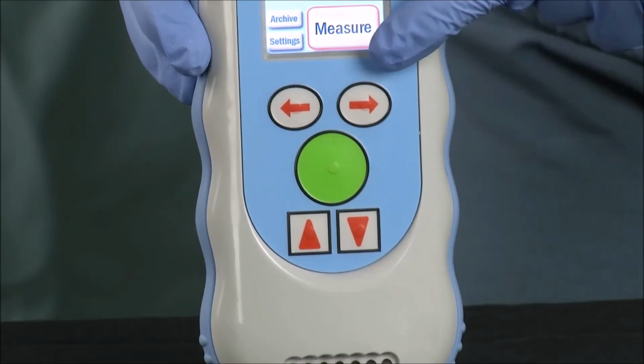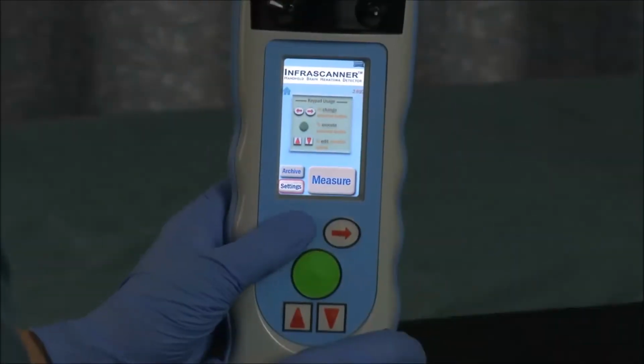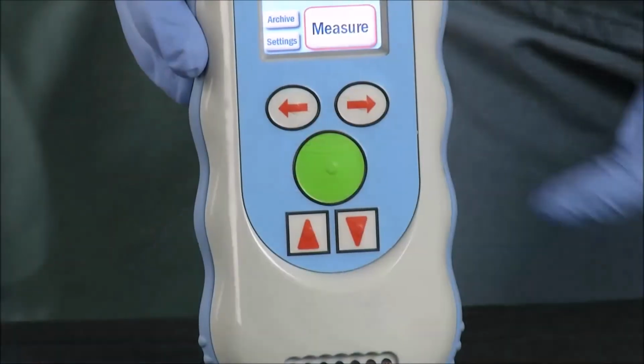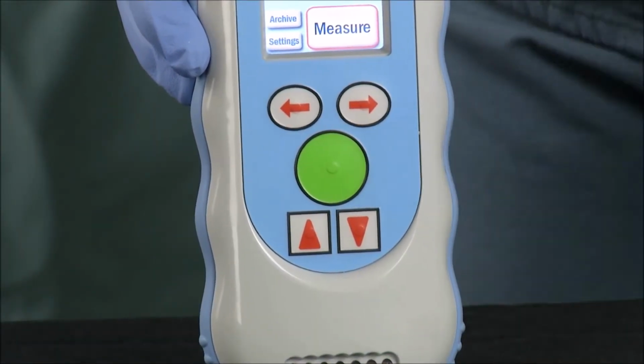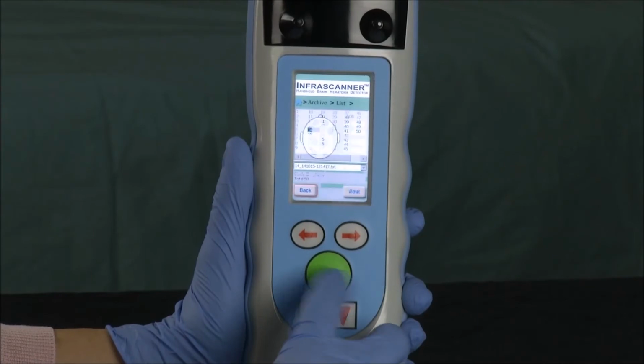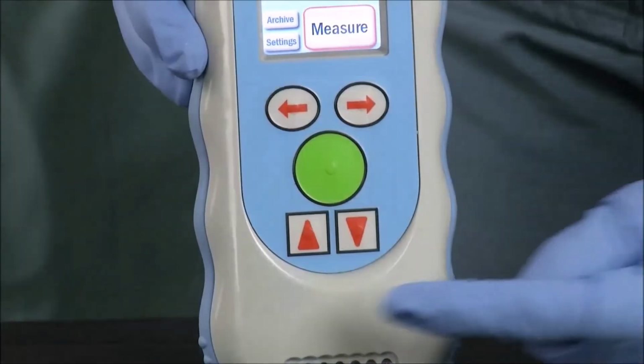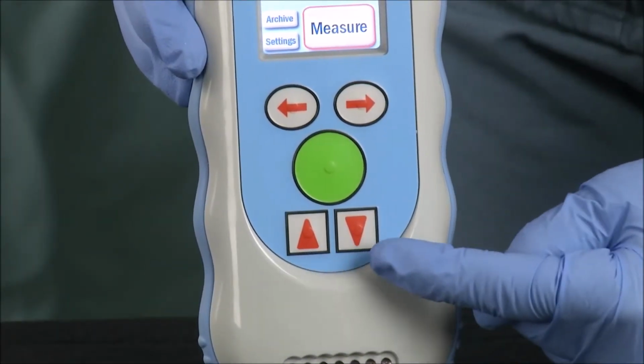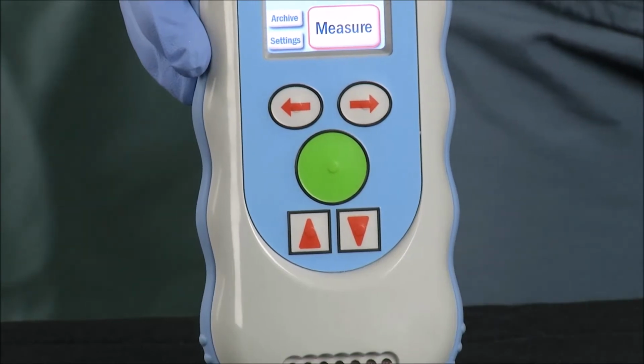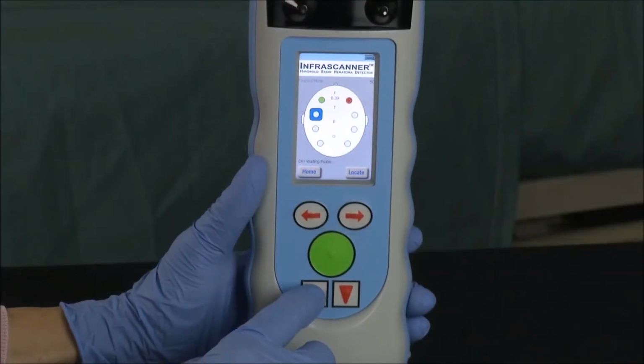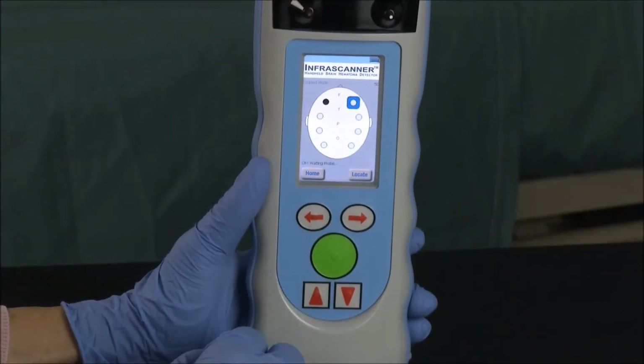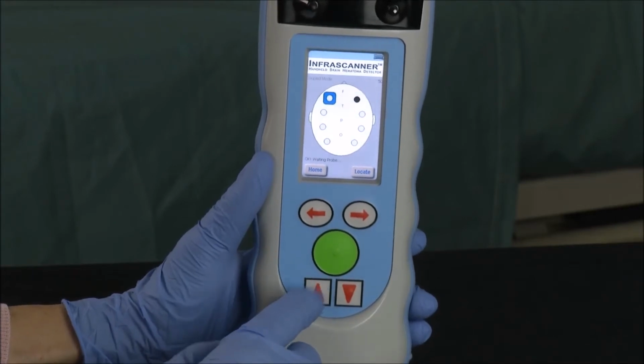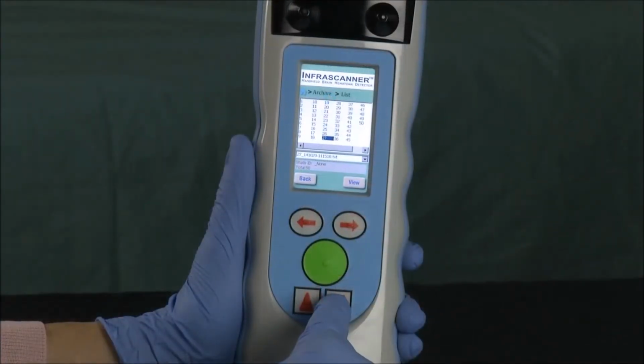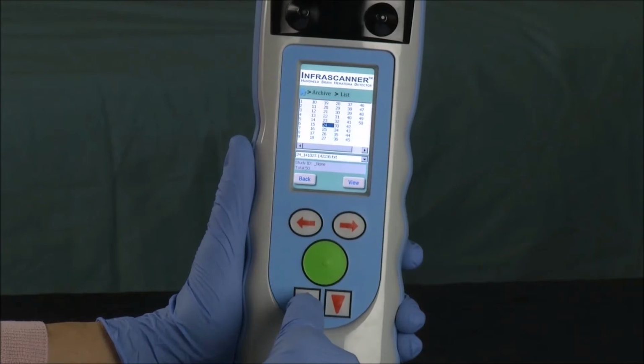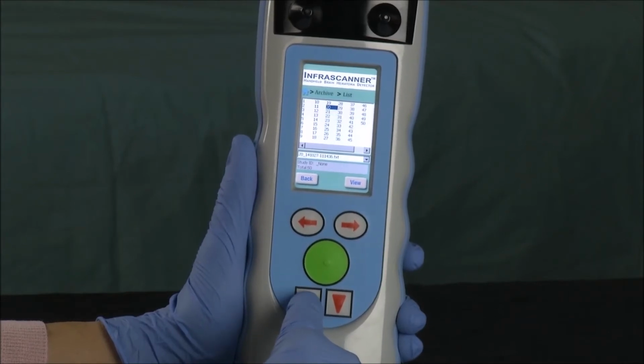The top left-right arrow keys navigate the operator through the infrascanner's on-screen menus. The center round green button is used to select or execute a desired task. The two up and down bottom arrow keys are used to edit a task. For example, you would use the up and down buttons when navigating back to a measurement point to rescan, or when navigating through the stored scans to select a desired measurement number in the archive screen.